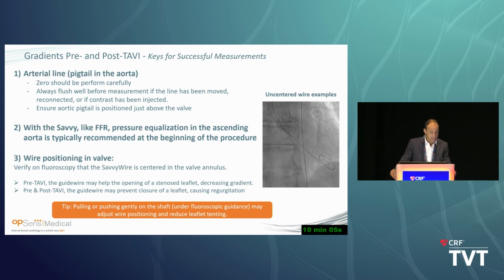Concerning the SavvyWire, like FFR, we like to equalize at the beginning of the procedure, but as I said, it's optional. For us, we like to equalize in the ascending aorta. It's easier with a second generation wire. So we pull back the wire from the ventricle into the ascending aorta. We match the aortic pressure with the pigtail, and then you just push your wire back into the ventricle. You're not losing your position. We typically do that at the end of the procedure too. At the end of procedures, typically it's not needed, but you can confirm that your pressures are still equalized.